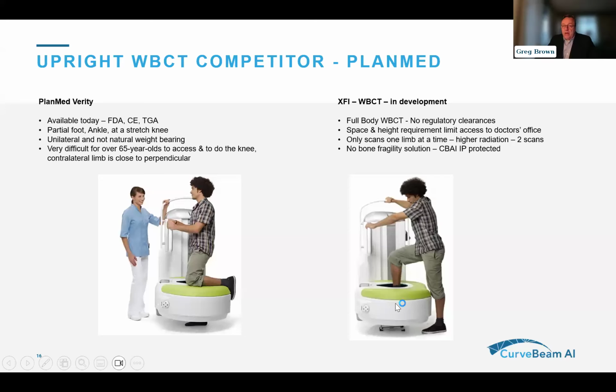Now, while all that weight's on that affected knee, that CT scanner will come up and the center of that panel has to reach your knee, just above your knee. So your other limb sits on the CT ring. So that CT ring is going to come right up. So it's quite a challenge to do the knee. Number one, it's unilateral. It's not natural weight bearing. It's quite difficult for the elderly to do this versus a high rise, open the gate, walk on, hold the handles. That's really the competitor we have today in weight bearing CT.